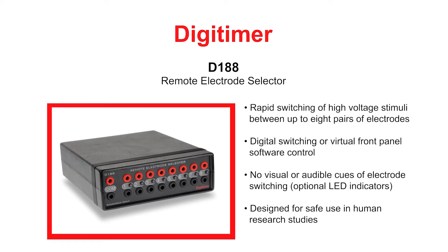The D188 Remote Electrode Selector allows high voltage stimuli from a single electrical stimulator to be directed to one of up to 8 stimulation sites. The D188 is supplied with Windows compatible virtual front panel software which permits manual switching between sites via a key press or mouse click.